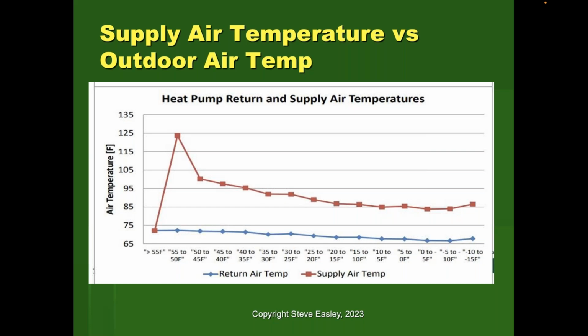But my point is that if you don't insulate and seal your ductwork, you can have lower discharge temperatures. And if the air coming out of that register is lower than your body temperature, it still might be 95 degrees, which is plenty to heat your house. But since it's cooler than your body temperature, you might say, wow, this seems kind of cool to me, and it doesn't feel quite right. So it's really important to help set customer expectations that the discharge temperatures out of a heat pump might be cooler than what they're traditionally used to.